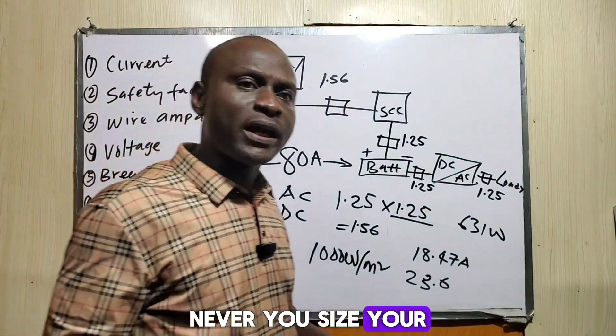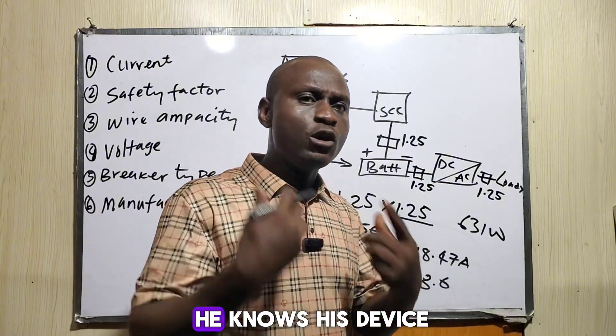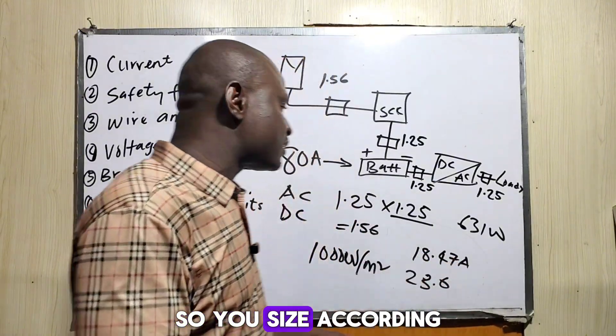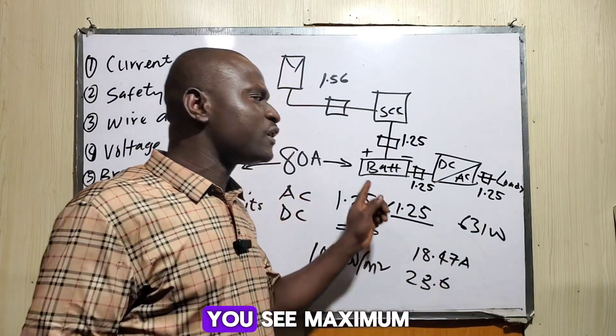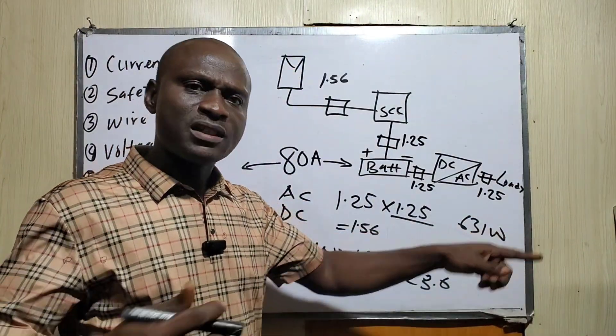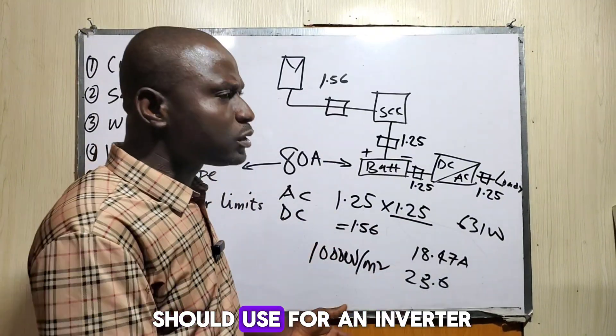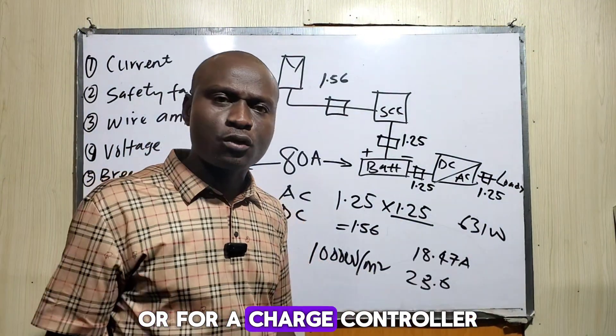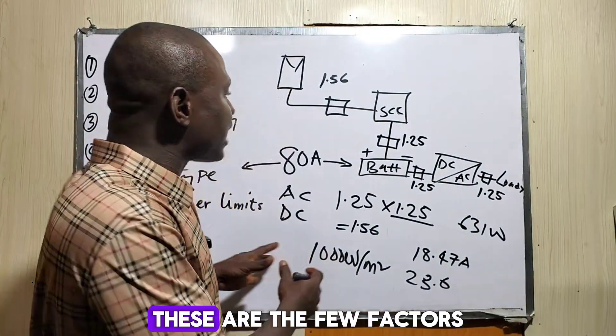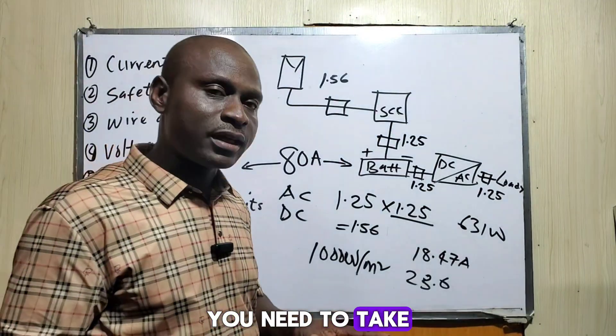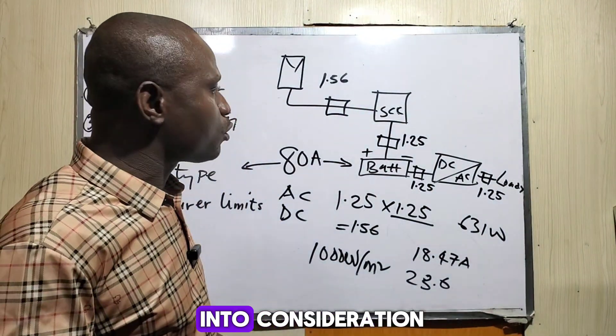Then there are manufacturer limits. Never size your breaker above the manufacturer's limits — the manufacturer knows his device. If you look at the back of your solar panel, you will see the maximum series fuse rating — the maximum breaker size you should use. Always stay within the manufacturer's recommendations. These are the key factors you need to take into consideration.